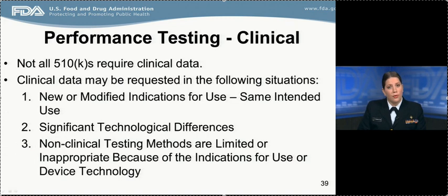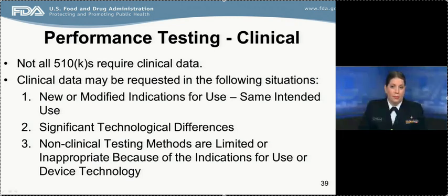I want to make a specific note on performance testing, clinical performance testing. Clinical testing is most often not required for 510(k) submissions. However, clinical data may be requested in the following situations. When you have new or modified indications for use, clinical testing may be needed. If you're making significant technological changes, that may also require new clinical data. Or when non-clinical testing methods are limited or inappropriate because of the indications for use or device technology. Please refer to the 510(k) program final guidance for additional examples and explanation on when clinical data may be appropriate.